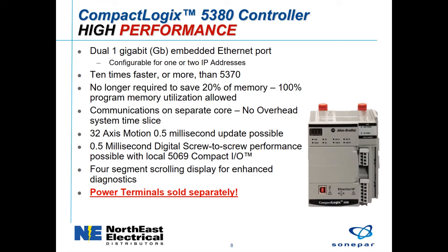Communications, there's no longer a system overhead time slice. It runs on a separate core, and it'll support up to 32 axes of motion. You need the motion enabled controller for that, with a 0.5 millisecond update rate as a possibility. Also for digital I/O, there's a 0.5 millisecond digital screw-to-screw performance. So if you turned an output on and read the input, that would take about half a millisecond.